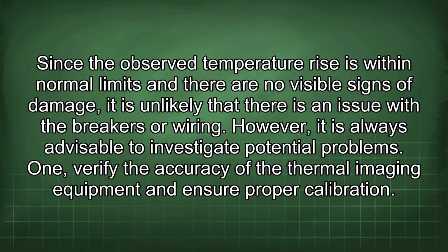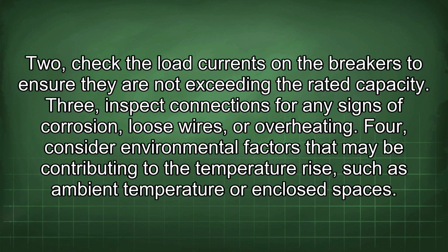1. Verify the accuracy of the thermal imaging equipment and ensure proper calibration. 2. Check the load currents in the breakers to ensure they are not exceeding the rated capacity. 3. Inspect connections for any signs of corrosion, loose wires, or overheating. 4. Consider environmental factors that may be contributing to the temperature rise, such as ambient temperature or enclosed spaces.